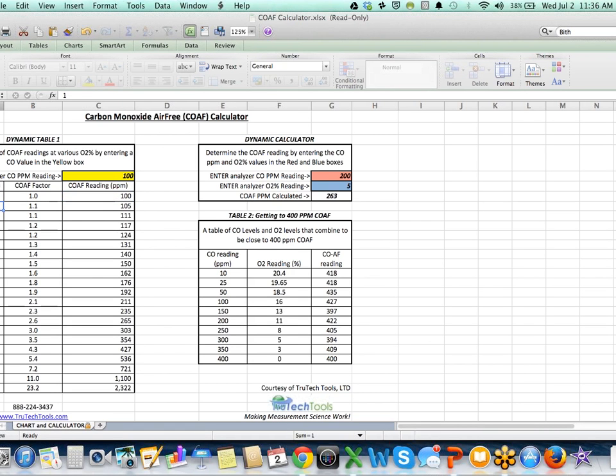But as you get into higher percentages of oxygen, you're working with a dilution. That oxygen is diluting the concentration of CO. So if you were to back it up to that stoichiometric wall, kind of walk backwards towards that wall that we showed in the previous graph, you would have a higher level. So again, CO air-free is always equal to or higher than the raw CO reading. And as you see, as you get up to higher levels, say like 10 parts per million, or excuse me, 10% oxygen.